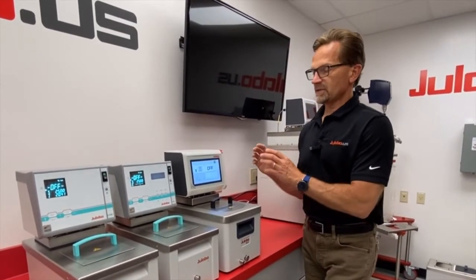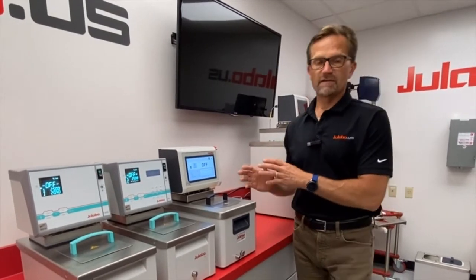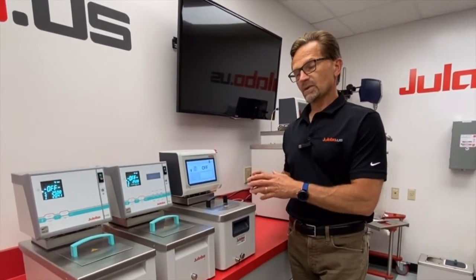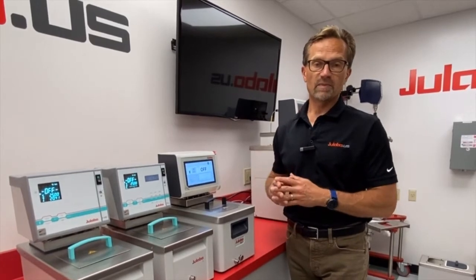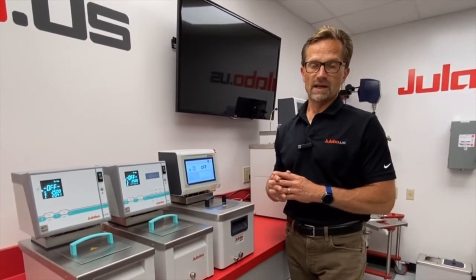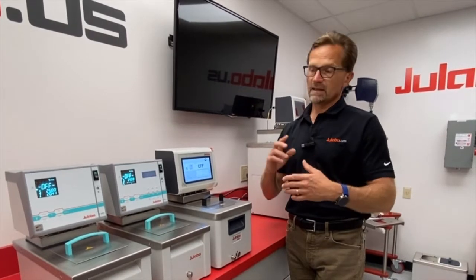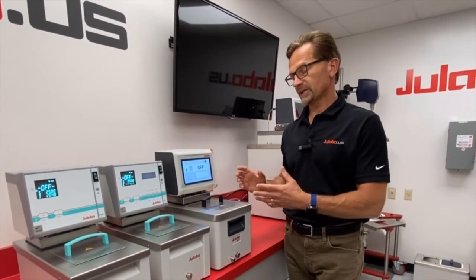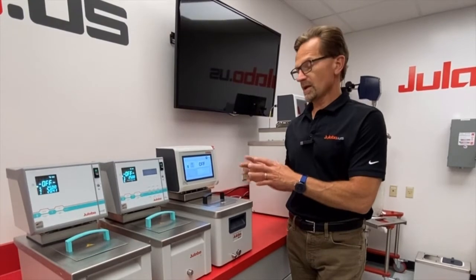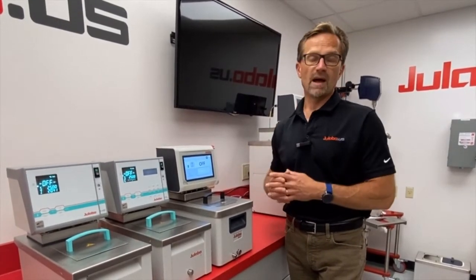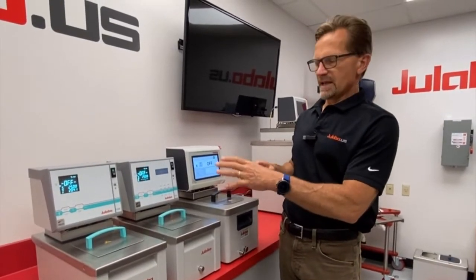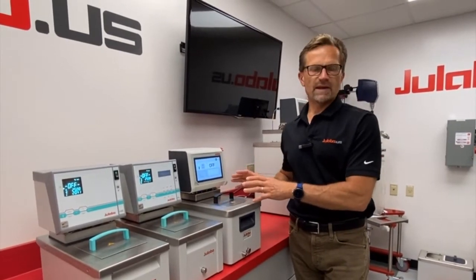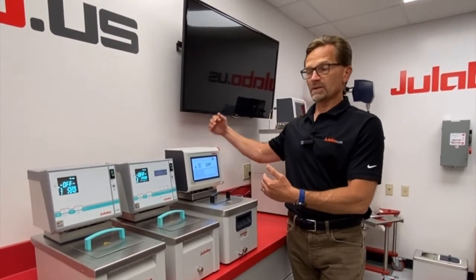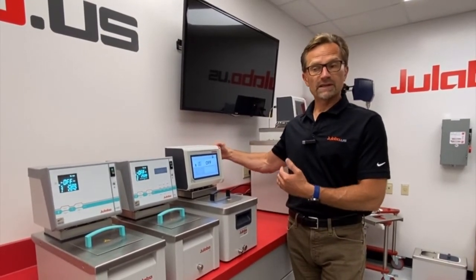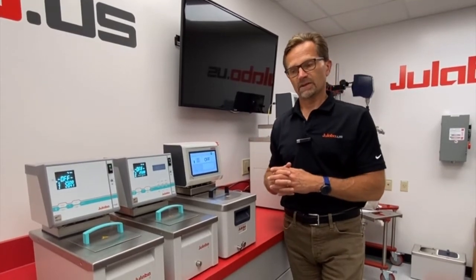One of the other benefits of the MAGIO is that it has a continuously variable pressure suction pump, which has a higher flow rate and pressure capability than the HE or the HL. So if you have an application that needs a faster flow rate or maybe a little higher pressure, the MAGIO unit is the way to go when choosing between these models. All units, the HE, HL, and MAGIO MS, have external PT100 sensor capability, which is important because you want to control from where that sensor is in your application. Your application temperature is what's important.